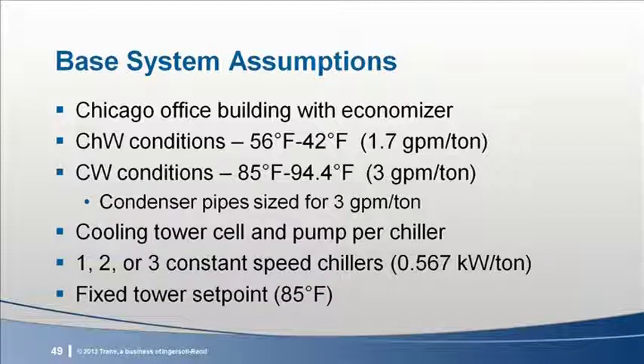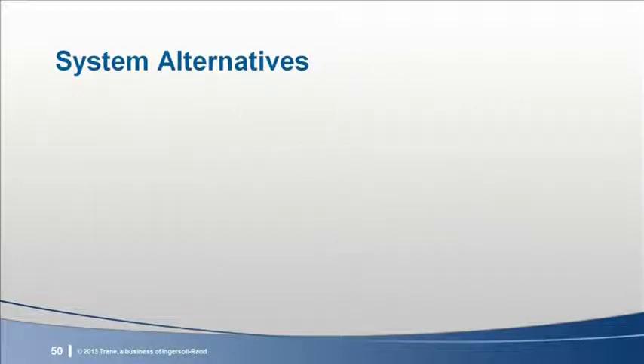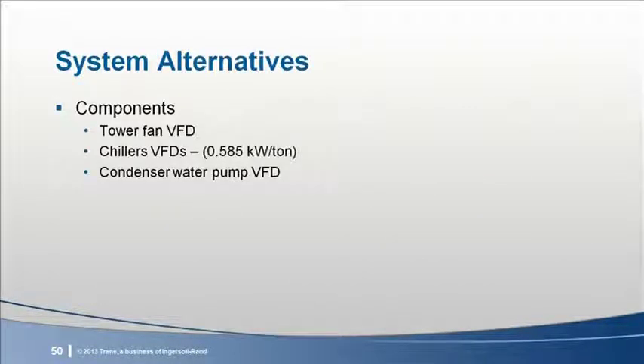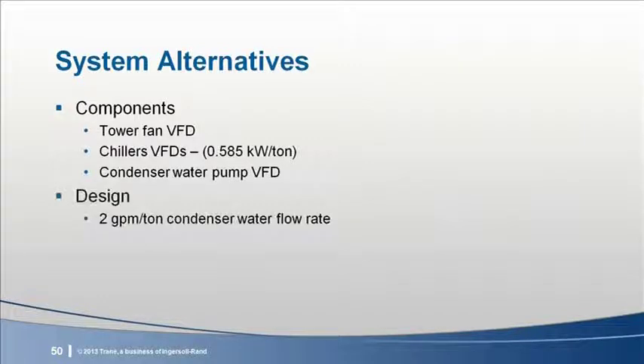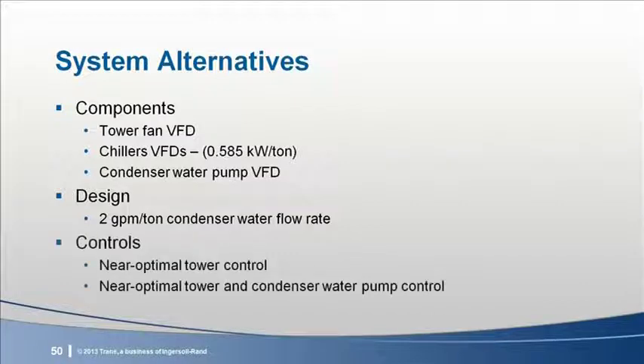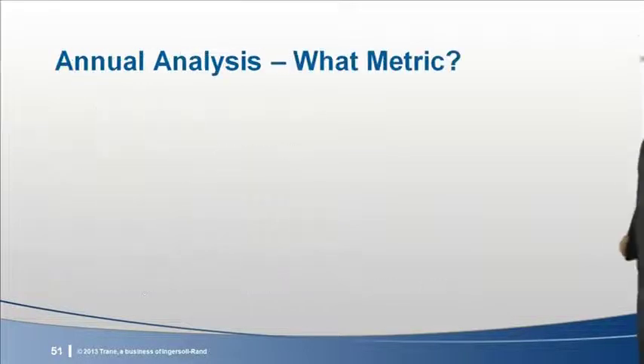Note the design condenser flow rate of 3 GPM per ton is something we'll reconsider, as are the chiller type and cooling tower set point. Since we often see building operators use a fixed set point, our base reflects that. As alternatives, we'll add a VFD to each component. We'll also consider a lower design condenser water flow rate. Then we'll examine just tower controls and a combination of condenser water pump and tower controls.